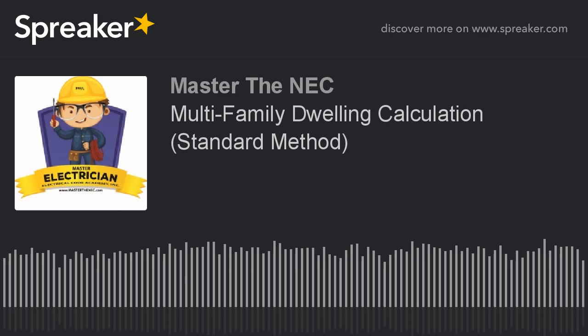The ranges: 70% of 33,000 is 23,100, so I should have 23,100 written down. I didn't have any load for the heating for the neutral because that's all 240 volt. The air handler, which is 120, and so that value that I had under the service goes directly under the neutral column, so that's 21,168. And of course, the largest motor application is also a 120 volt load, so that 294 VA also gets added to the neutral.